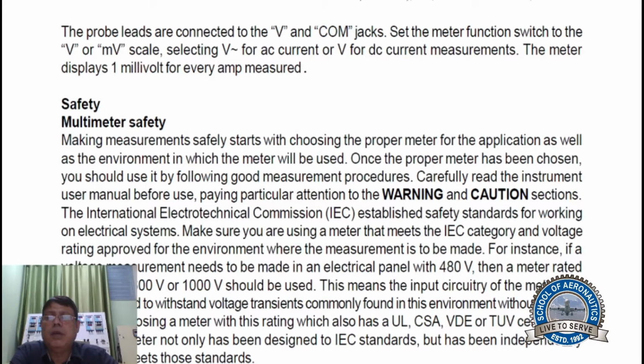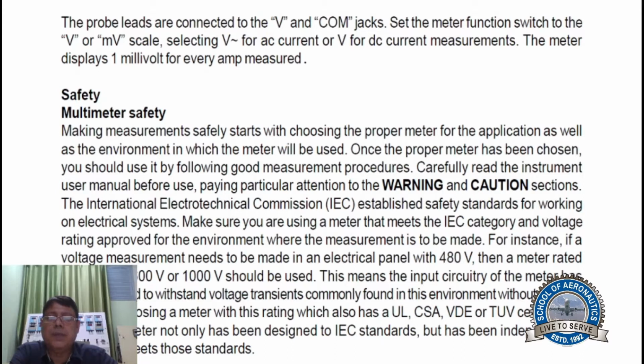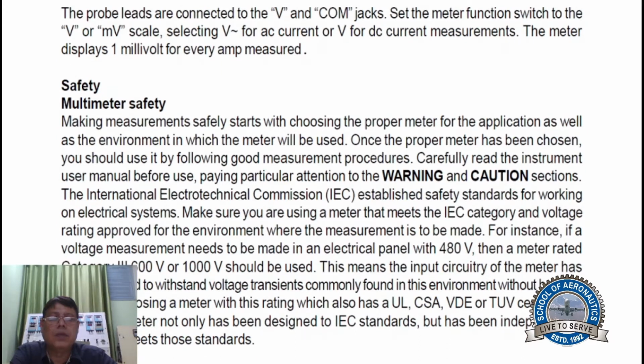The International Electrotechnical Commission (IEC) established safety standards for working on electrical systems. Make sure you are using a meter that meets the IEC category and voltage rating approved for the environment where the measurement is to be made. For instance, if a voltage measurement needs to be made in an electrical panel with 480 volts, then a meter rated category 3 600 volts or 1000 volts should be used. This means the input circuitry of the meter has been designed to withstand voltage transients commonly found in the environment without harming the user.